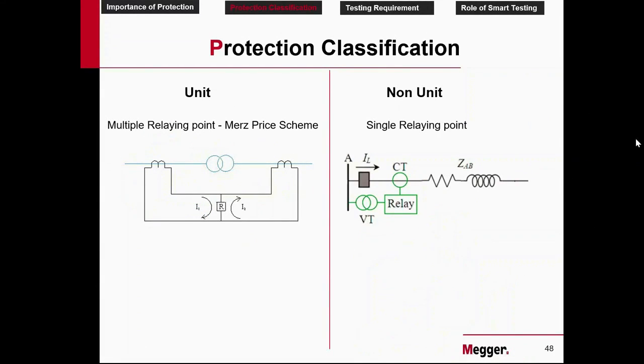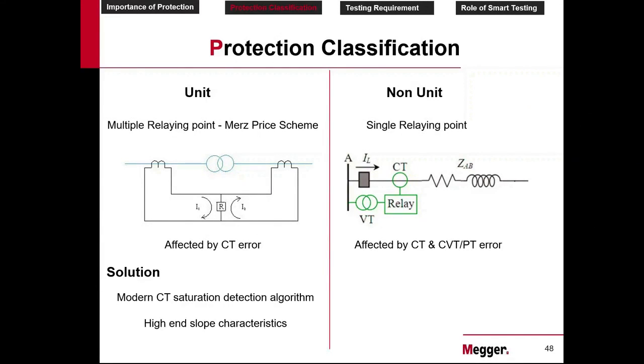I remove all the drawing and let's see what are the challenges that they face. The unit protection is affected by CT error and the non-unit protection is affected by CT and PT error. The solution is modern CT saturation detection algorithm, high-end slope characteristics. Here the solution is pilot-aided scheme and non-pilot-aided scheme. So these are the two types of classification. If you have understood these two, you can understand all the 95 types of protection function in ANSI code definition. Even the protection function defined in Indian Railway, we will come to that after this presentation. Whatever falls or different types which is defined in Indian Railway comes under either this unit protection or non-unit protection.